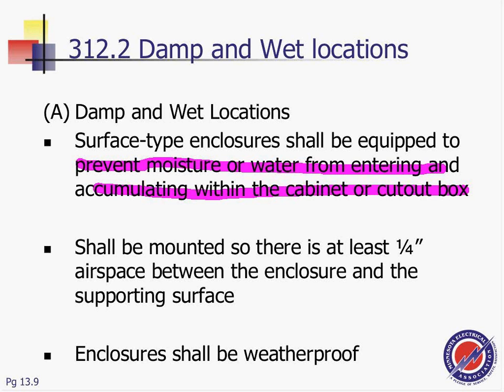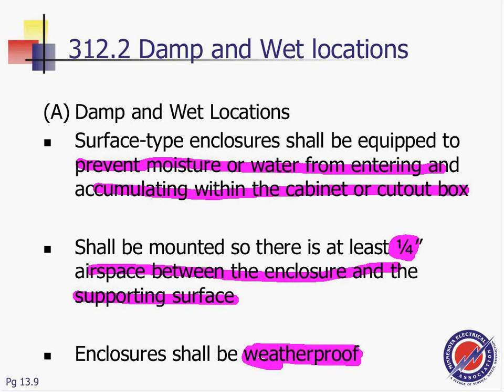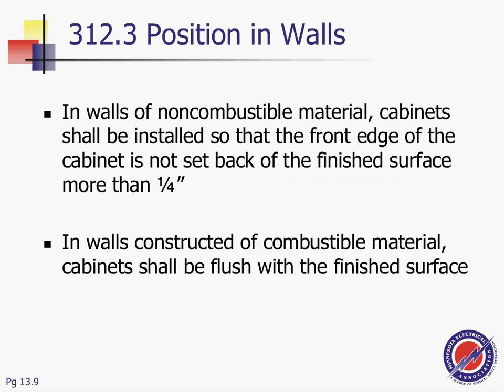This would be asked in the general exam: a 1/4 inch space between the enclosure and the supporting surface. They want you to maintain that. It will be mounted, again, in a damp and wet location. They want you to mount it to prevent rust and so forth, keeping a space of 1/4 inch. Sometimes we put wood or something right behind it to maintain that space, guys. The enclosure shall, again, be weatherproof. If it's in a wet or damp location, it has to be weatherproof. That's for all enclosures installed in these areas.